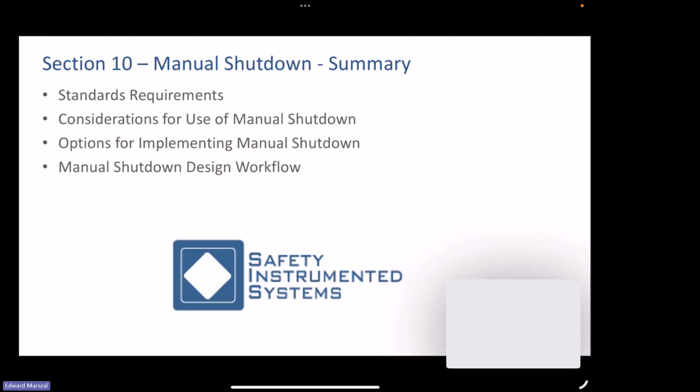I don't have enough time, so it provides no value. And I could do it another way in the BPCS or shutdown of the plant. Other final elements obviate the hazard and make it unnecessary. There are a variety of means of doing it, but if I could roll back to the beginning of the question, putting in equipment to back up something that never fails is a justification in and of itself that can sit in the general requirements.